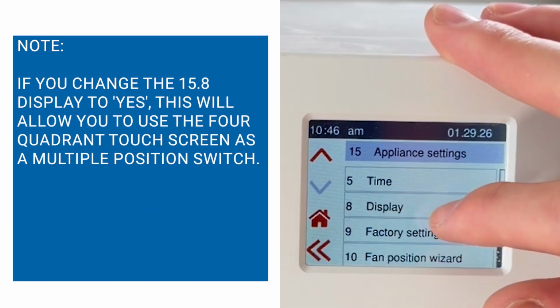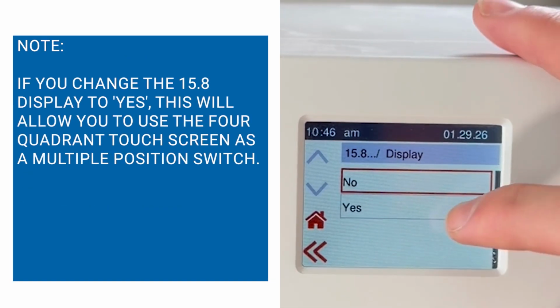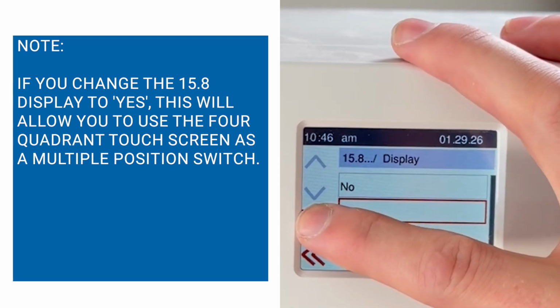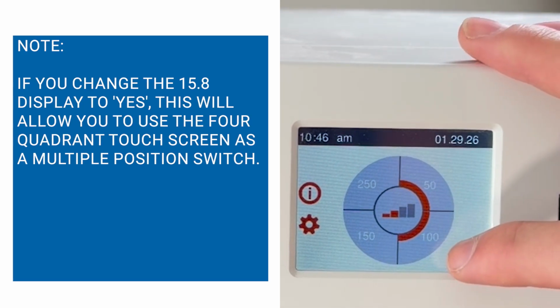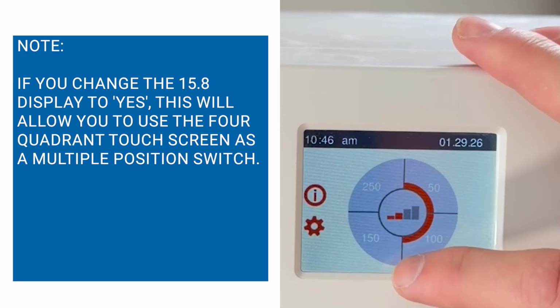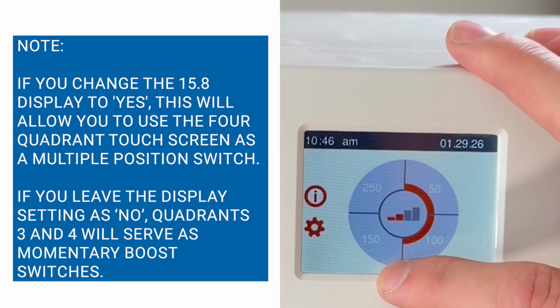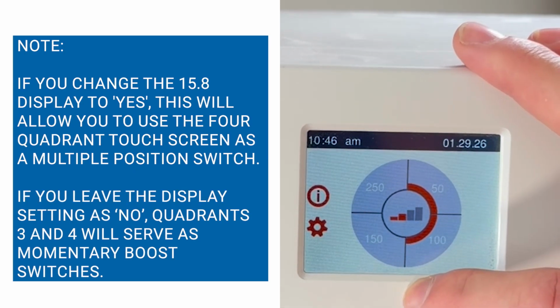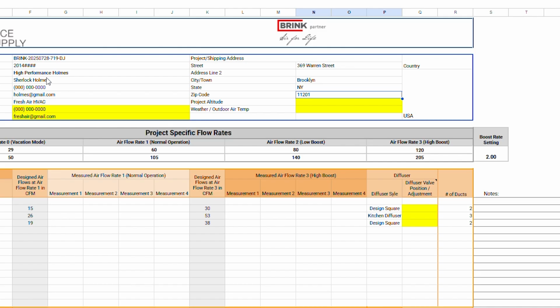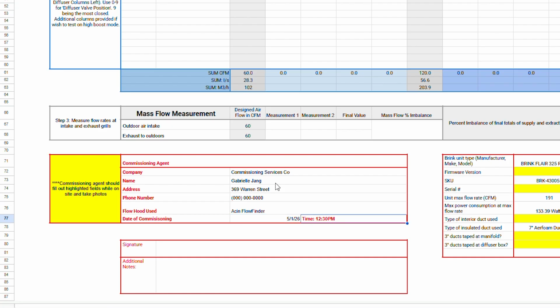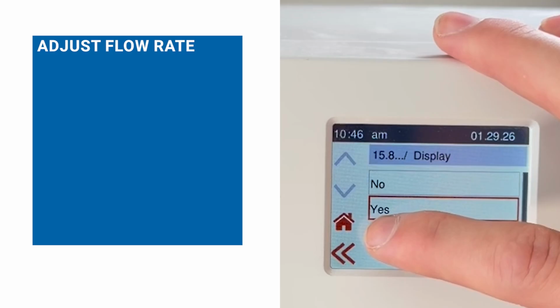Note that if you change the 15.8 display to Yes, this will allow you to use the 4-quadrant touchscreen as a multiple position switch. If you leave the display setting as No, quadrants 3 and 4 will serve as momentary boost switches. On the commissioning sheet, the commissioning agent should also record the outside conditions and date and time of commissioning. Next, the flow rates should be programmed.